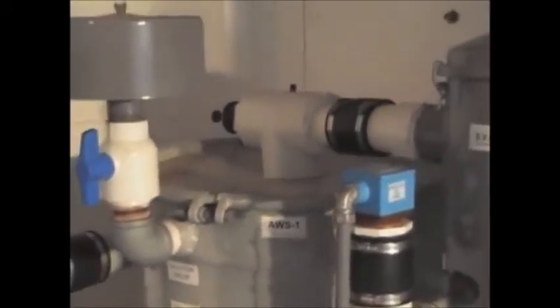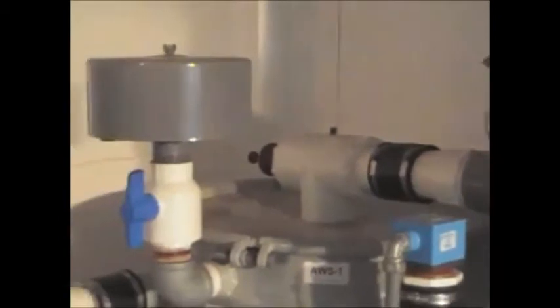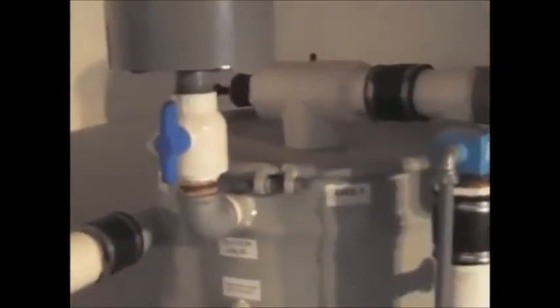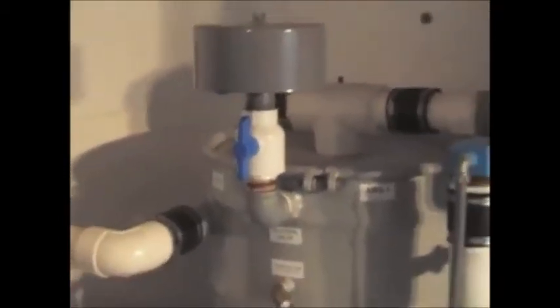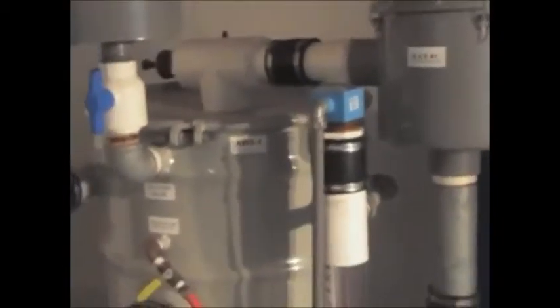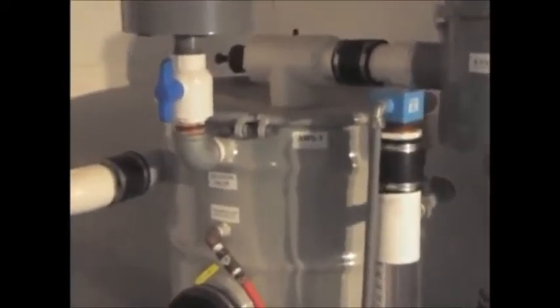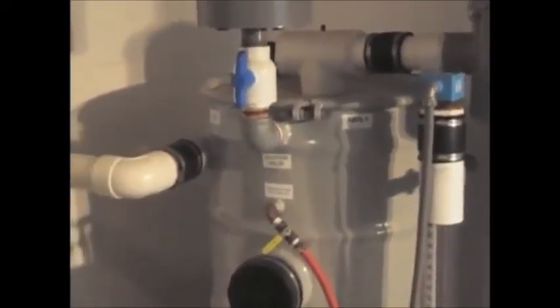And so the order of things when we get started here is we will turn the system on, and then we will test or demonstrate the operation of the SVE portion with flow rates and vacuums. And then we will demonstrate the compressor building pressure and the cooling of the aftercooler. And then finally, we have a small 55-gallon drum out in the back where we'll introduce water into the air water separator, and you can see that it operates that way.